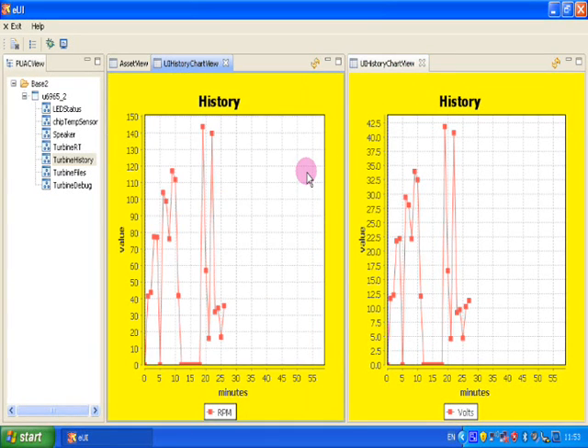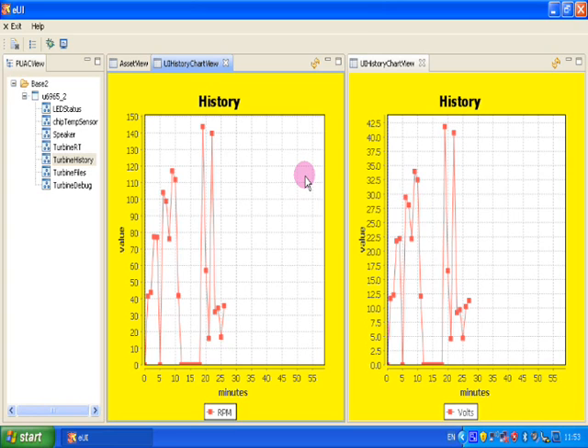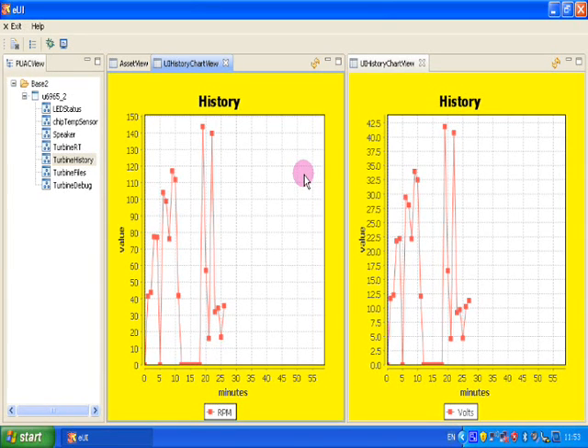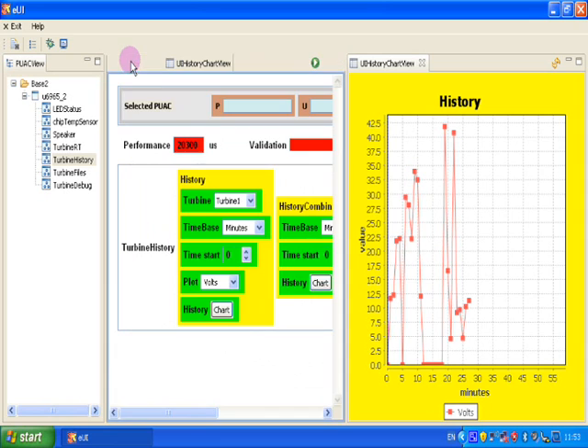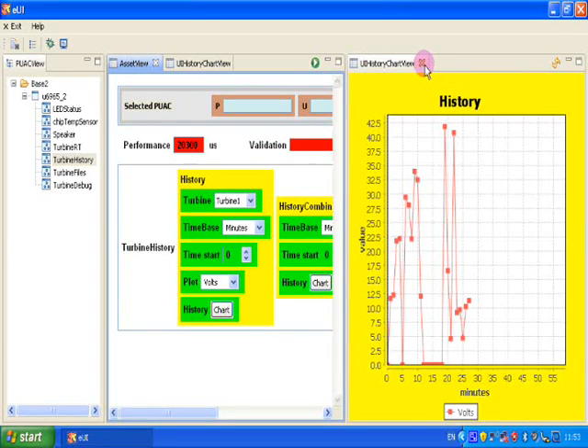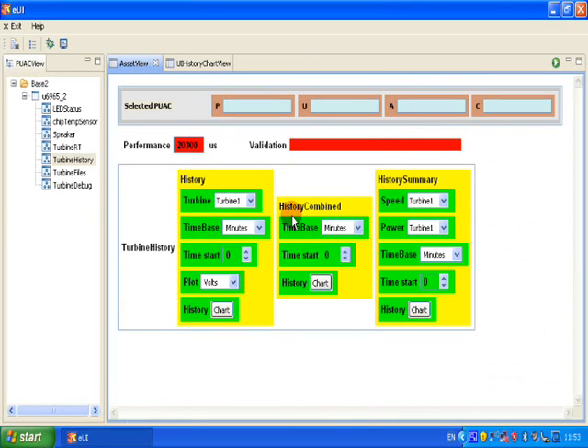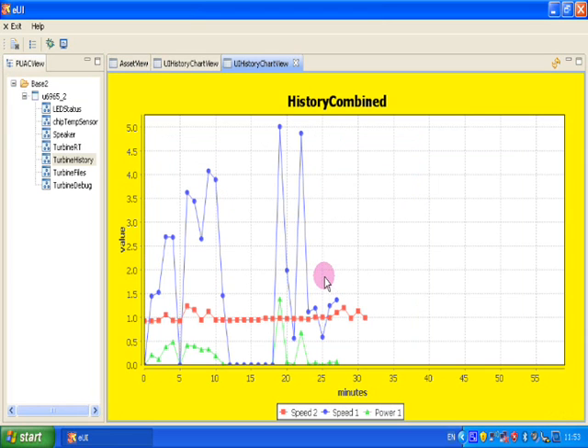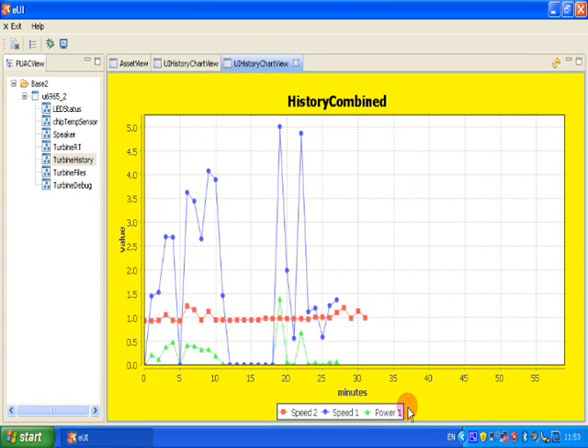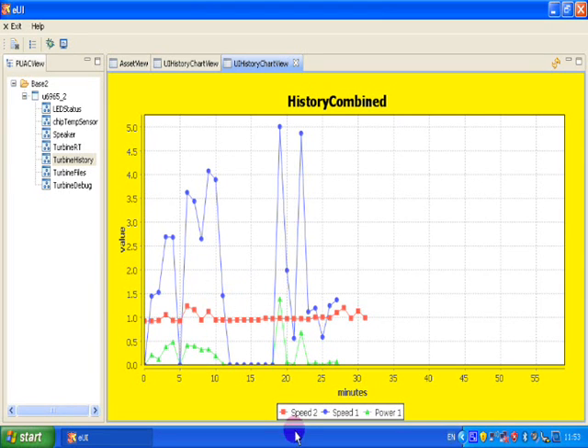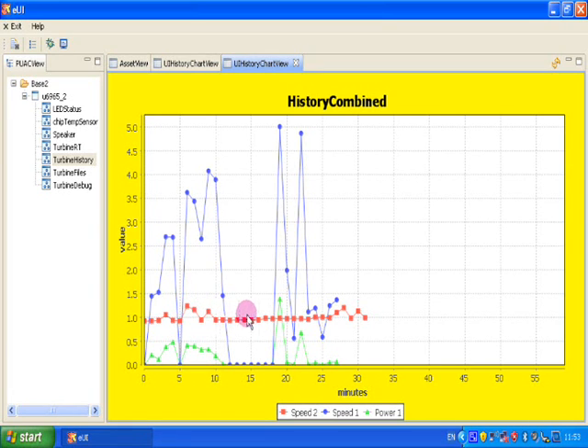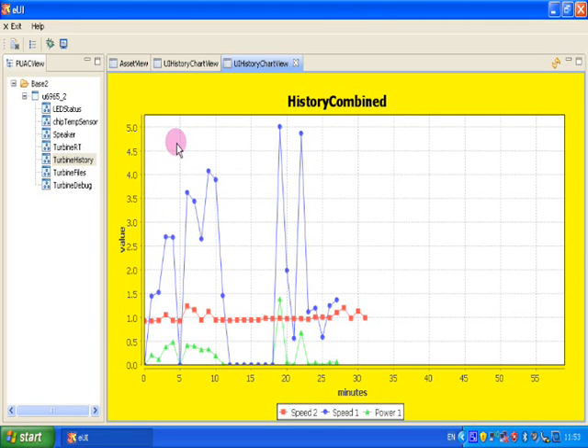It would be nice to actually see some data on the same plot, instead of having to pull up multiple plots. And that's what the combined view will do for us. So let's have a look at that. So here we see multiple sets of data on the same time x-axis. We can see two speed outputs on this plot. So we could use this to calibrate one anemometer against another. And let's have a look at the final view in the history.